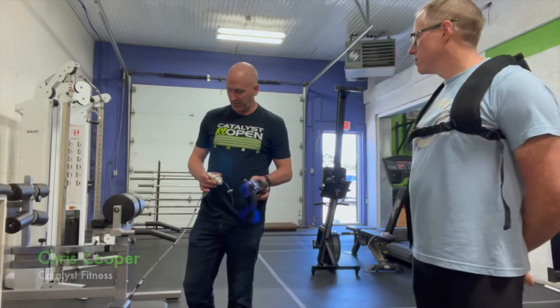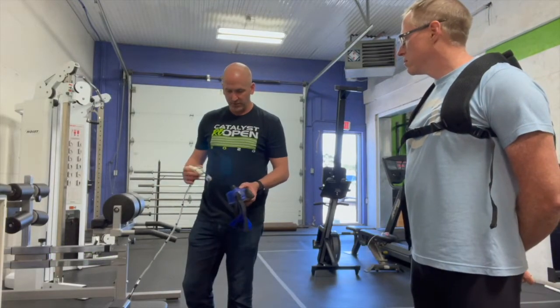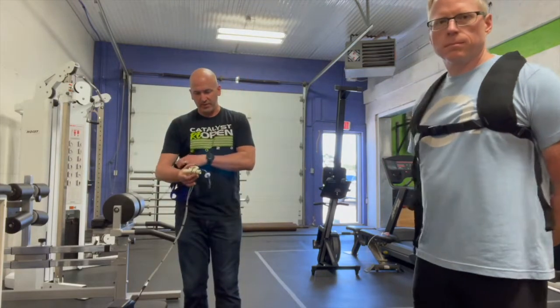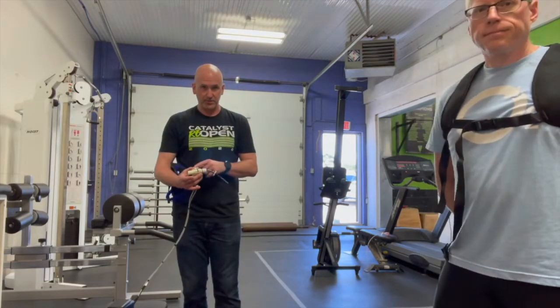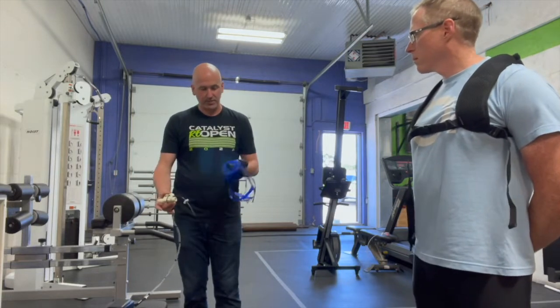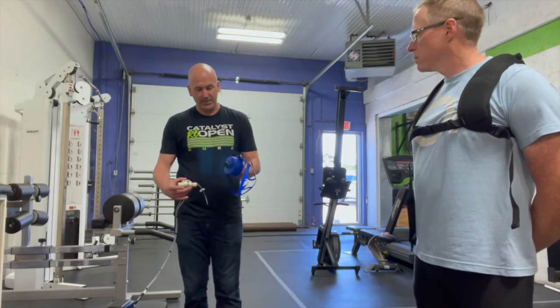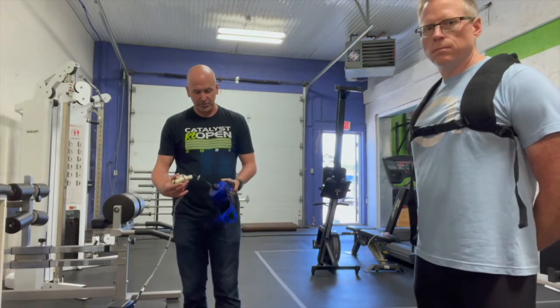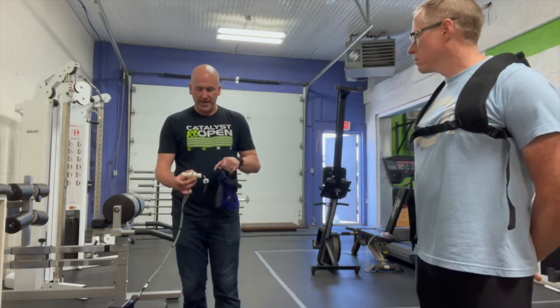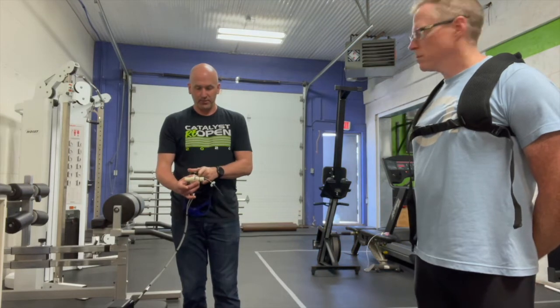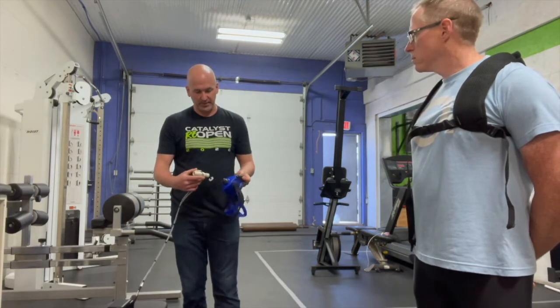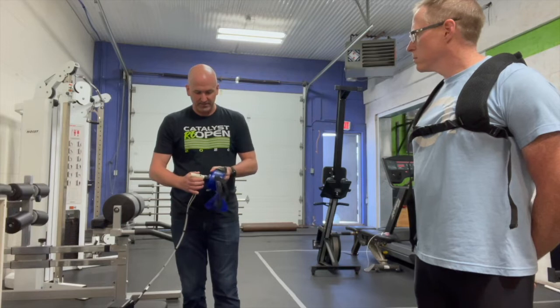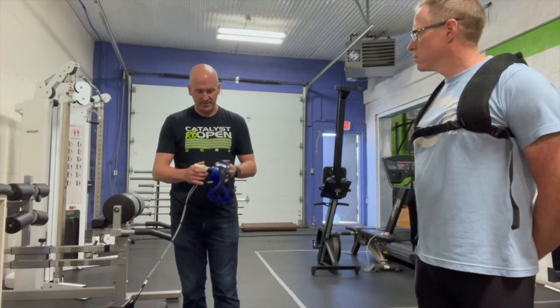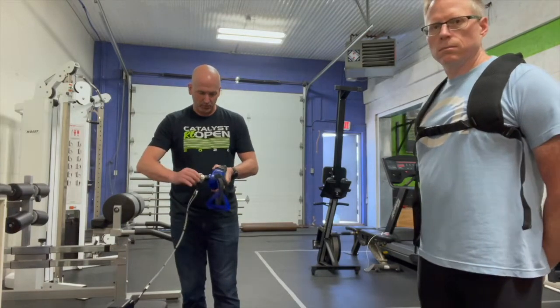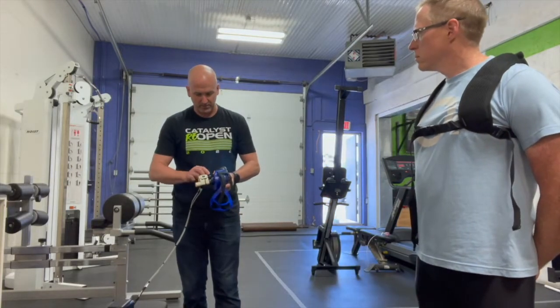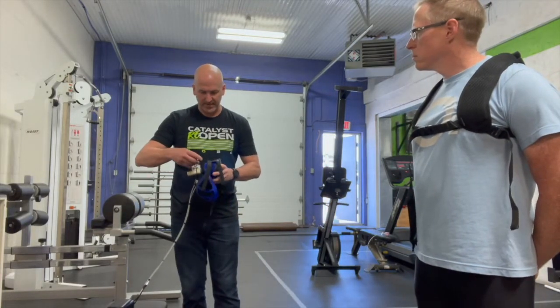The next step is to put the mask and the flow sensor together. So the important thing to understand is that one end of this flow sensor is going to go into the mask. So we fitted our adapter that has a nozzle to accept the flow sensor tube. But the first thing we're going to do is look for the end of this that has a rubber ring on it. The rubber ring is going to get put into the adapter on the front of the mask. And if you kind of twist and push a little bit, you will hear a distinct click.